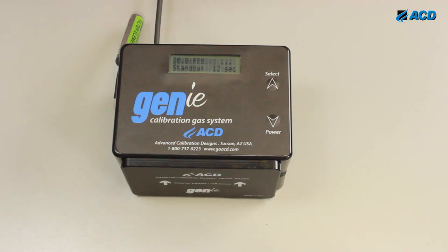All right. So after this counts down past 10, it's going down. When it gets to 0, it's stable and ready to calibrate. So here you'll see, instead of flashing stabilizing, it'll now read, okay, we're making 20 parts per million chlorine. That's your hint, your clue that we're ready to calibrate. So now it's ready to calibrate.